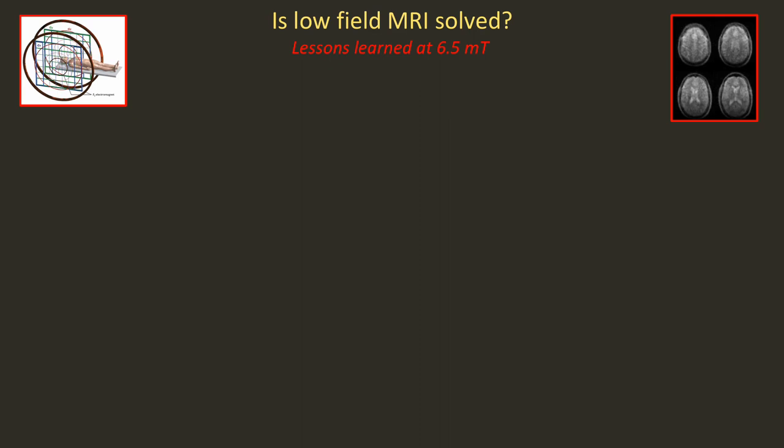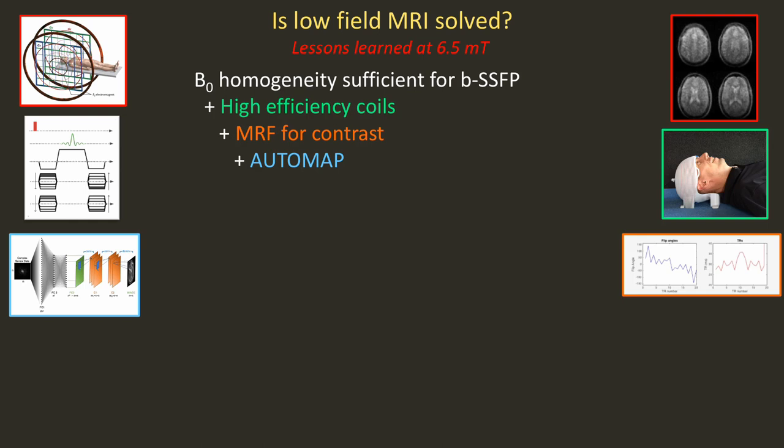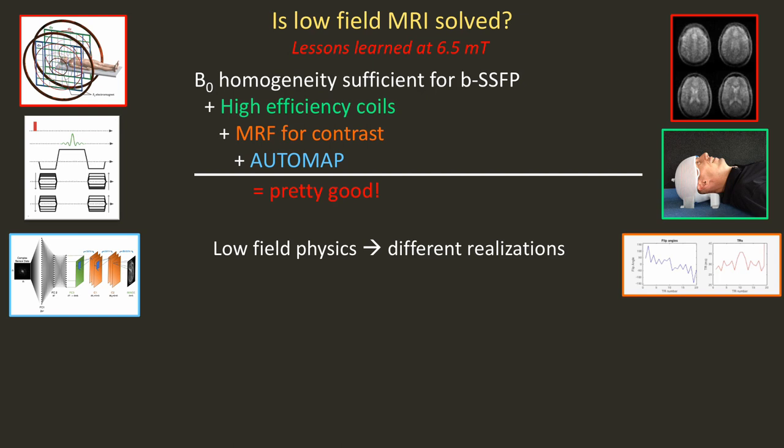Have we solved low-field MRI? We've learned a lot at 6.5 millitesla. If you have homogeneity sufficient for SSFP, high efficiency coils, fingerprinting for contrast, and AUTOMAP to get below the Johnson noise dominant regime, we actually do pretty well. Once you understand the low-field physics, you can think about different realizations.